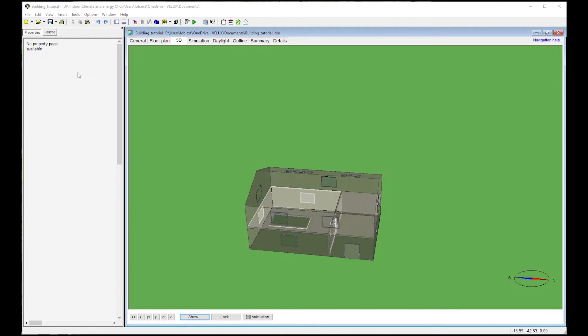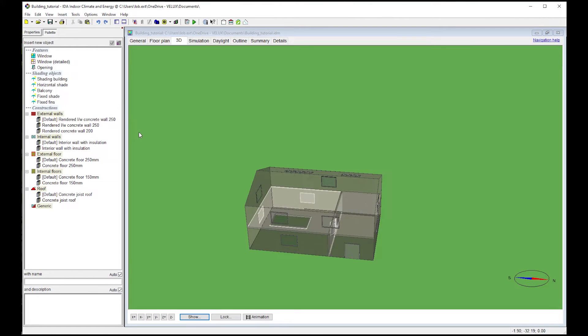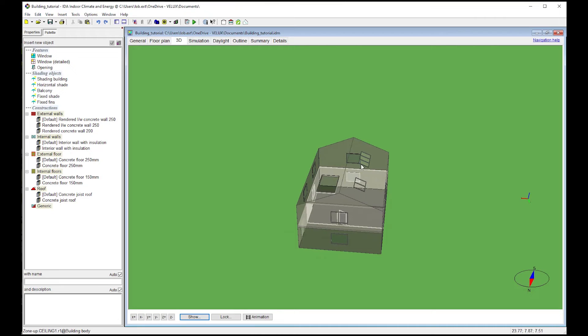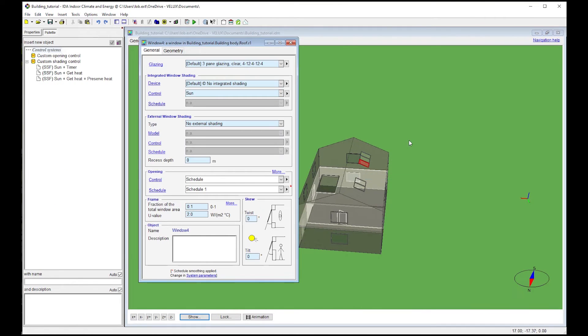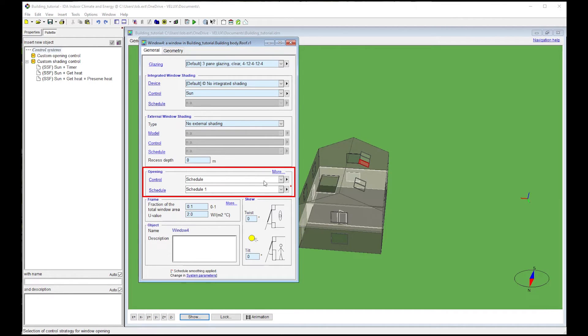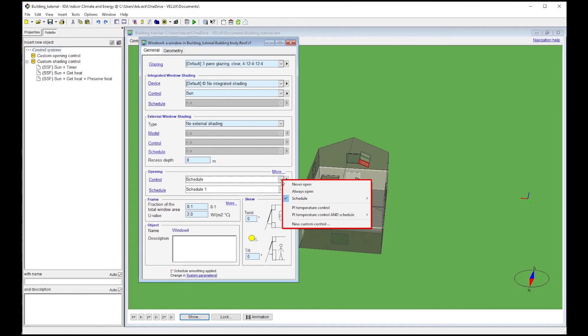Now let's move on to the windows. From the palette on the left, it is possible to add two different types of windows – window and window detailed. There are no sensible differences between these two window types for simulating natural ventilation in buildings of this size; differences would appear only for high-rise buildings. Looking at the opening control strategies in the window interface, the relevant inputs are under 'opening'. The control modes include: never open, always open, schedule, PI temperature control, and PI temperature control with schedule.